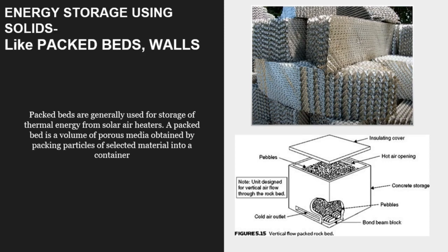As you can see in the diagram given below, it has a hot air opening at the top, the cold air inlet at the bottom, and pebbles tightly packed inside. As the cold air enters, it has to move vertically up against gravity through the pebbles and then come out of the hot air opening. The pebbles inside are closely packed, so they absorb a lot of heat energy from the air or fluid which is moving, thus trapping and storing a lot of heat energy in the process.